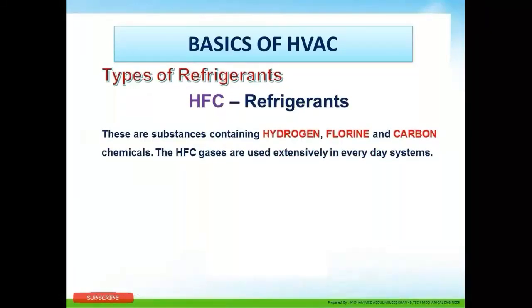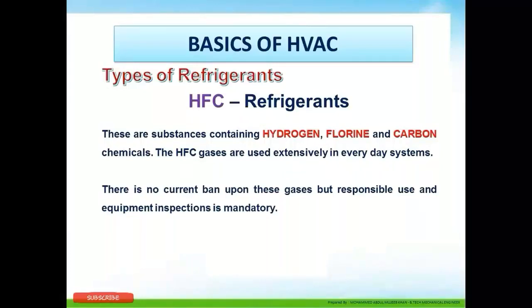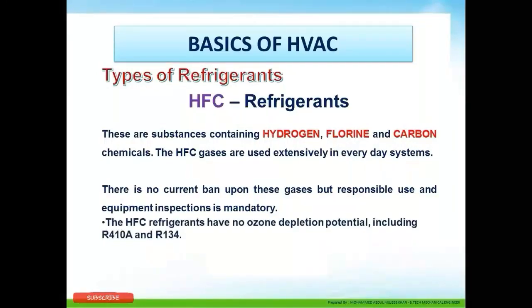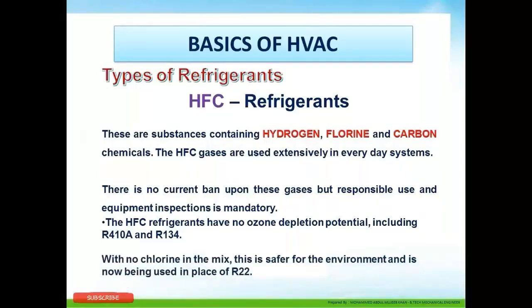HFC refrigerants are substances containing hydrogen, fluorine, and carbon — with no chlorine in the mix. HFC gases are used extensively in everyday systems. There is no current ban on these gases, but responsible use and equipment inspection is mandatory. HFC refrigerants such as R410A and R134A have no ozone depletion potential, making them safer for the environment and now being used in place of R22.